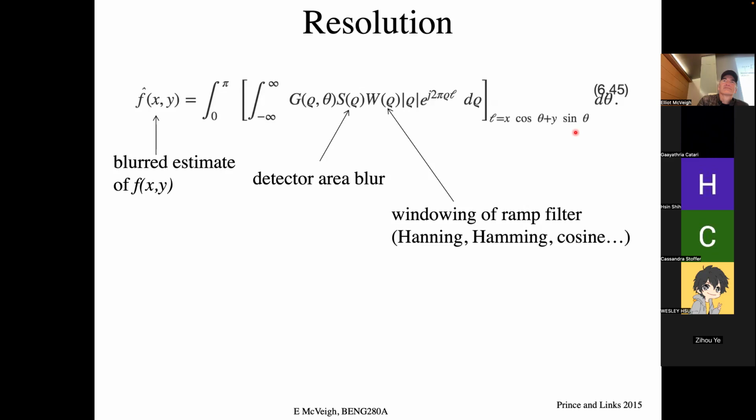And then when we inverse Fourier transform that, that's when we get the convolution. So let's say I just keep doing that process. I change that line a little bit, do it again, change the line a little bit, do it again. Take 1,000 lines through the Fourier transform of the object. Now I've got a lot of points, so I should know what the Fourier transform of the object is. They're in polar coordinates, so we take the inverse Fourier transform of that data now, and it gives me the object, or an estimate of the object.